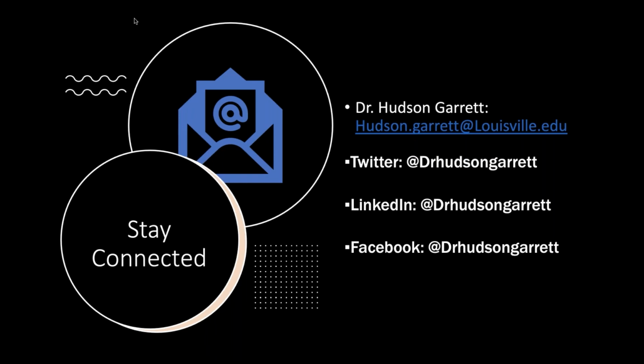Now, the other piece that I'll add to this, and this is just more my personal view, is that the reason this whole conversation is coming up is that there's a known inconsistency with HLD, and the results associated with that, as well as cleaning. And so people are saying, well, if we can't trust HLD, let's just do the next best thing, which is let's zap the whole scope and actually have a sterile device, right? And even if the scope itself could withstand sterilization, it doesn't mean that it's going to actually get rid of everything. Because if we don't properly pre-clean a device, we don't get rid of all the gross organic soil and bioburden, that scope is still going to be contaminated. It may have sterile gunk on it, but it's still got gunk, and no patient is going to want that used in them, nor would any of us. And so I think that's something to think about as well.